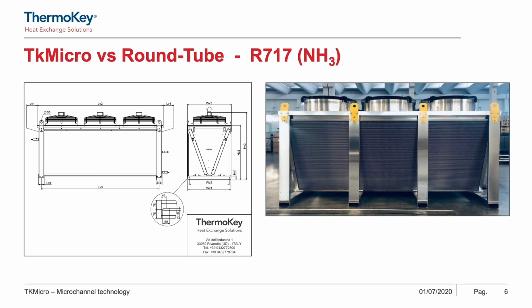For example, let's consider for a second the reuse of ammonia. Ammonia is becoming more and more interesting on the refrigeration market, and the main problem of ammonia is that it's not compatible with copper. So anytime we consider ammonia, we need to use stainless steel. And immediately the comparison between microchannel and round tube heat exchanger is made between stainless steel and aluminum.